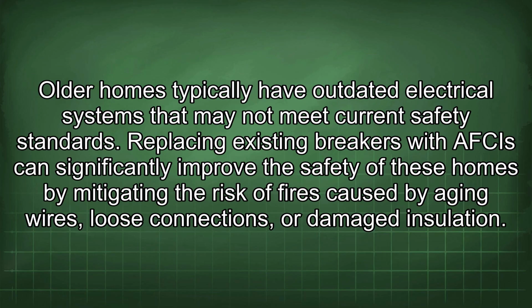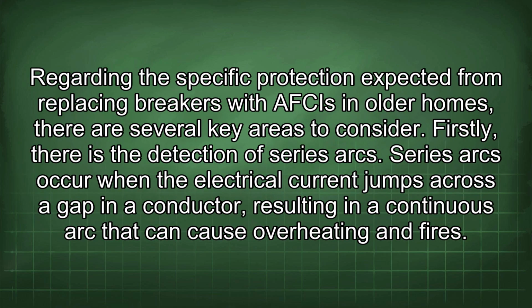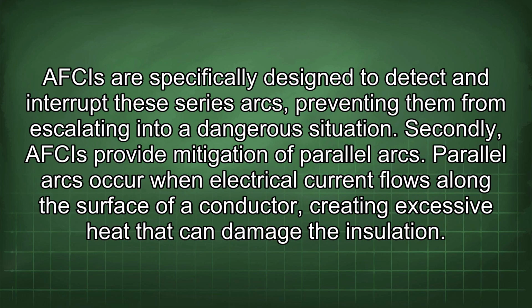Older homes typically have outdated electrical systems that may not meet current safety standards. Replacing existing breakers with AFCIs can significantly improve the safety of these homes by mitigating the risk of fires caused by aging wires, loose connections, or damaged insulation. Regarding the specific protection expected from replacing breakers with AFCIs in older homes, there are several key areas to consider. Firstly, there is the detection of series arcs. Series arcs occur when the electrical current jumps across a gap in a conductor, resulting in a continuous arc that can cause overheating and fires. AFCIs are specifically designed to detect and interrupt these series arcs, preventing them from escalating into a dangerous situation.